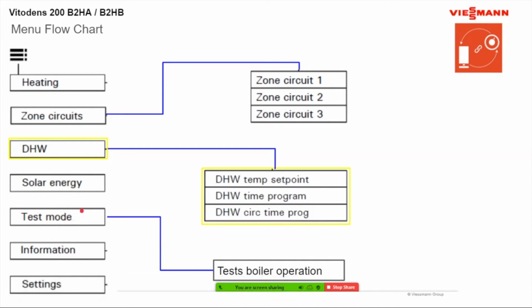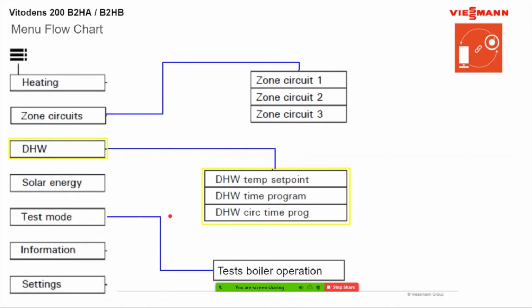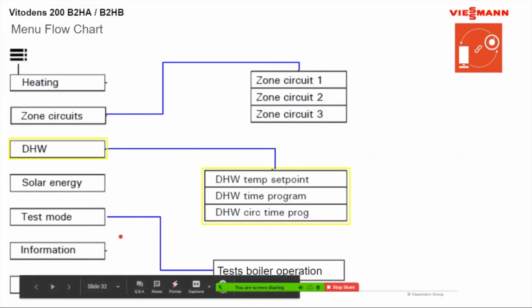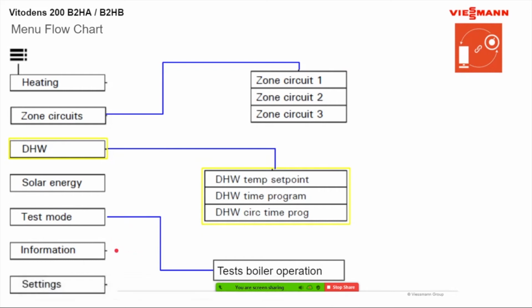Test mode, that's if, say, you want to get to the job and see if the boiler fires, or before you leave, you want to see the boiler fire and your pump come on. That's your test mode. What that really is for, in Europe, they have people that do the efficiency test through the chimney, and they come in, you have to push that button so they can go up there and do the efficiency test. If they find that it's not meeting efficiency, they give you a certain amount of time to fix the problem, and if not, they come and take your boiler away. I know that'd be nice here, right? I'm still working on old boilers from the 1800s, believe it or not, that were converted from coal to oil.